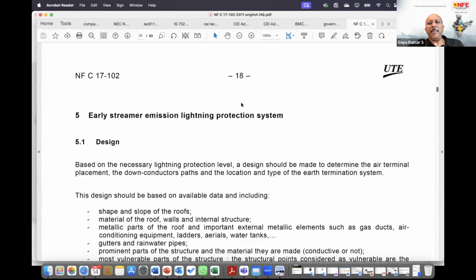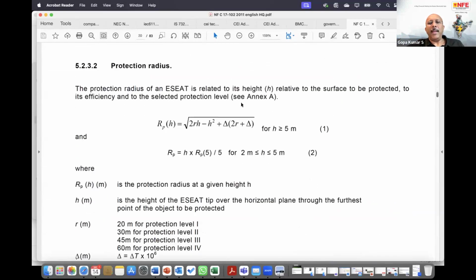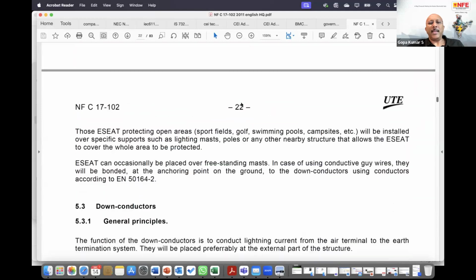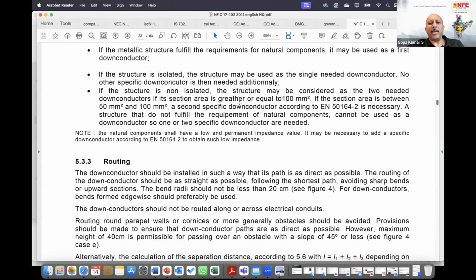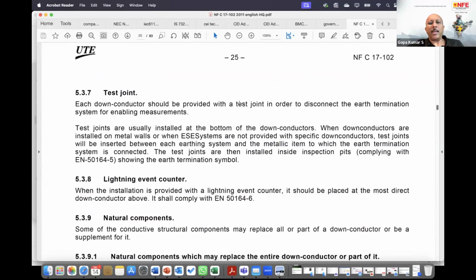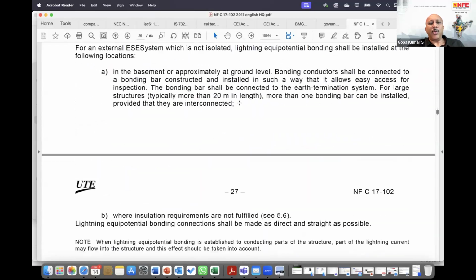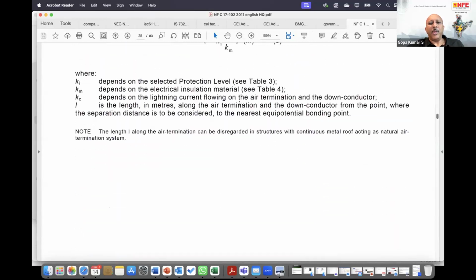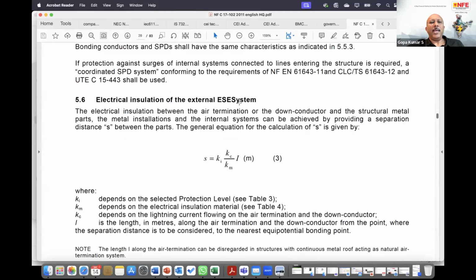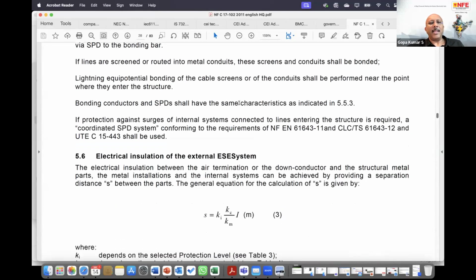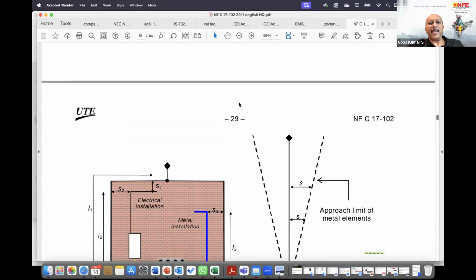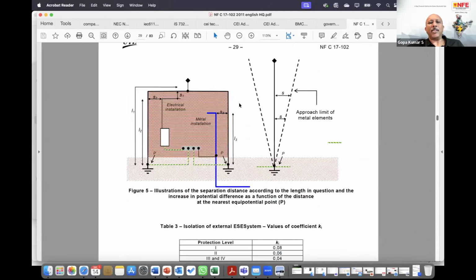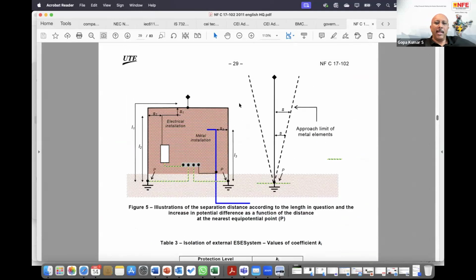Whereas the ESE manufacturers in India come and explain to us saying that, sir, one rod protects 120 meters, with one down conductor and one earth electrode. Go to the same NFC standard, go to clause number 5.6, electrical insulation of external ESE lightning protection system. There is a picture and the explanations. Please read this particular explanation.